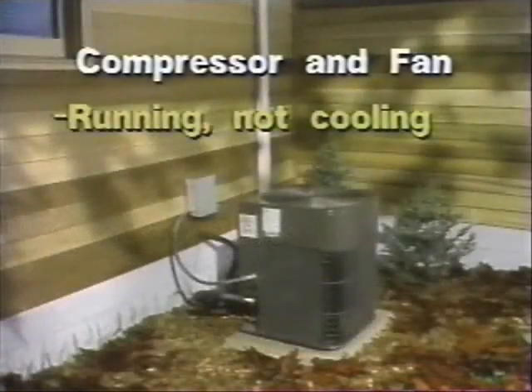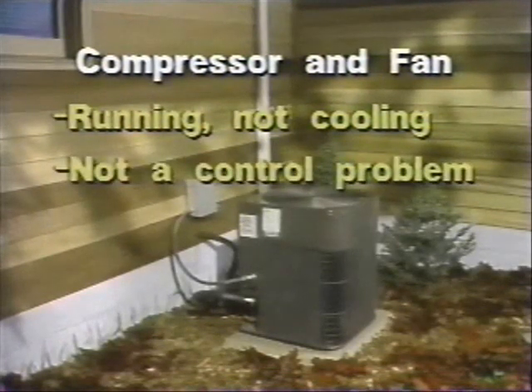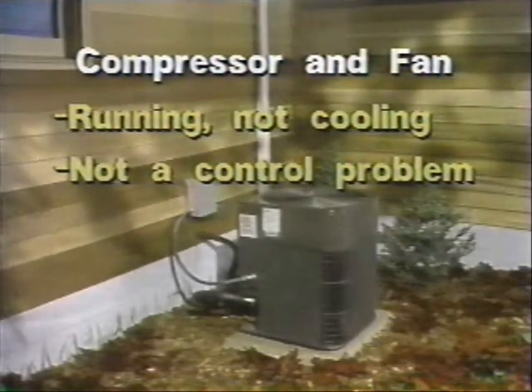If the compressor and fan are running but are not cooling properly, it's probably not a control problem. You'll probably want to start with the refrigeration system. If the system doesn't start at all, or starts and runs without stopping, the problem could be in the contactor.